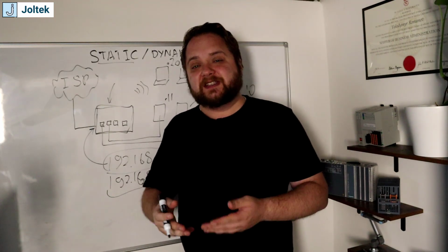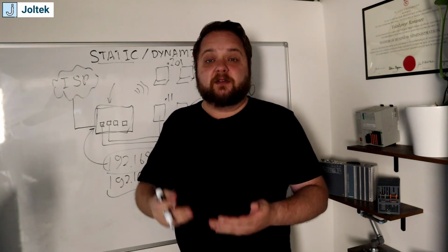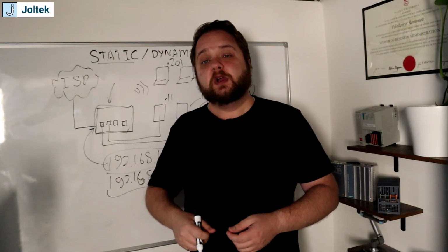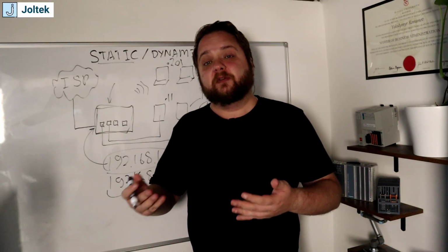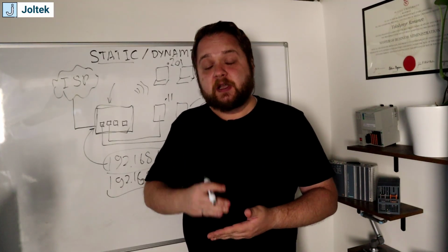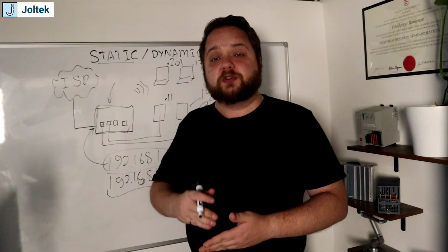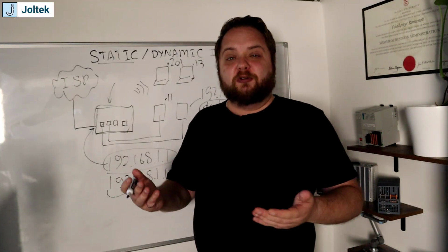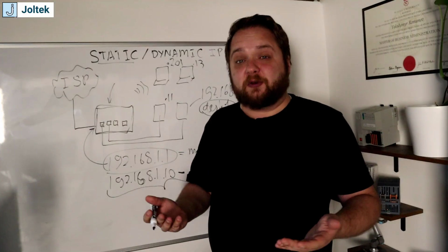So you're going to physically, or I guess manually, configure the device using whatever software of choice, or using, as I've shown you, the front panel of the VFD. You're going to set the IP address and you're going to set the subnet mask, and you're usually going to set the gateway. Now, there's no other explanation for that reasoning.